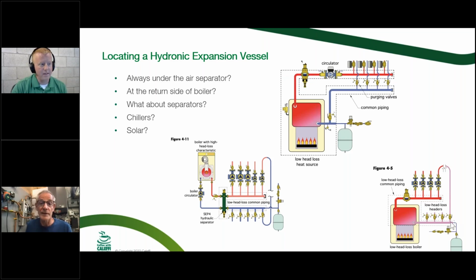Yeah, definitely something to think outside the box. Like Bob said, you don't have to hang it always on the supply side. Obviously, if you were to look at it from this side, you'd put it on this side of the boiler. If you wanted it on this side of the separator, put it right before that circulator there. But over here, you've got this nice long header, and you're pumping away from it. It just looks a little different because you've got this long header, this big low velocity zone here, and a little bit of header here. But the pressure drop from one point to the other is pretty minimal.